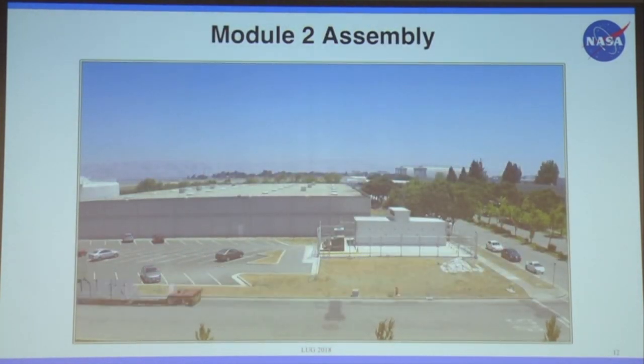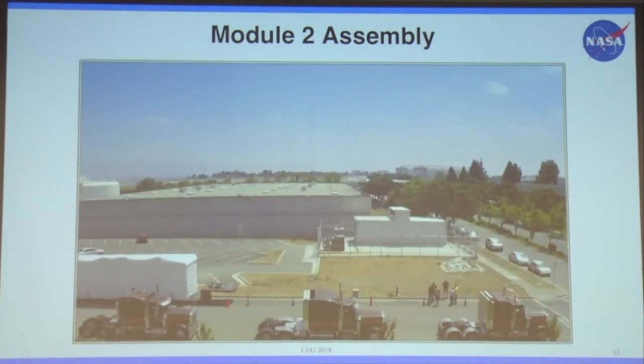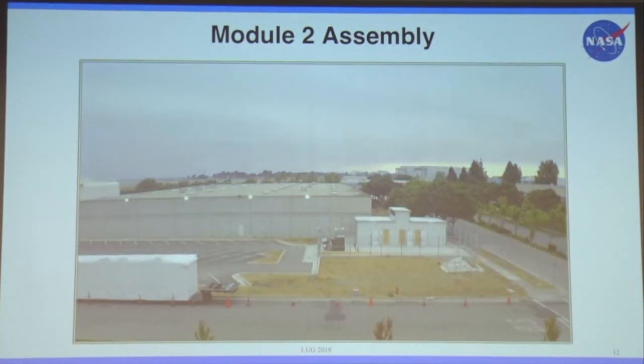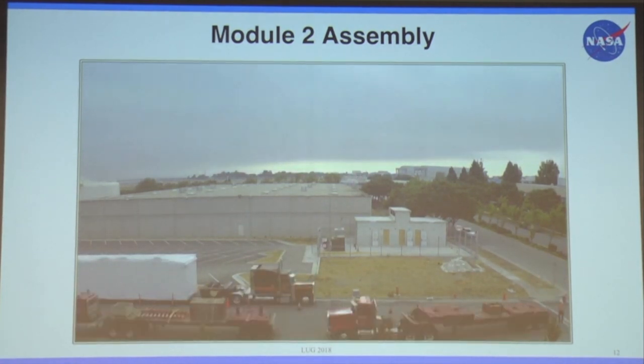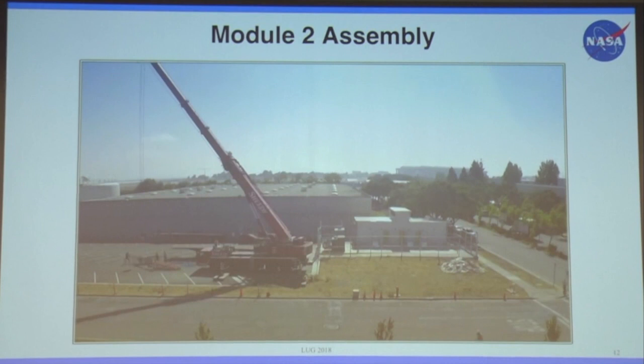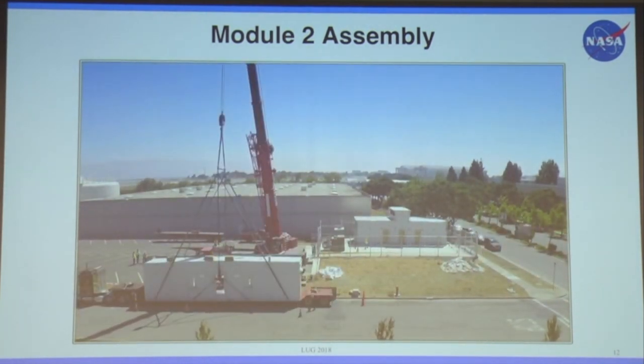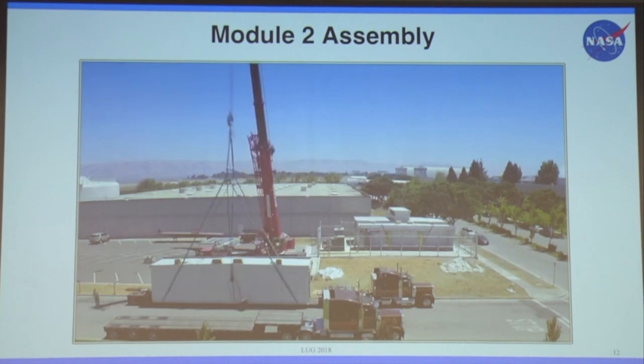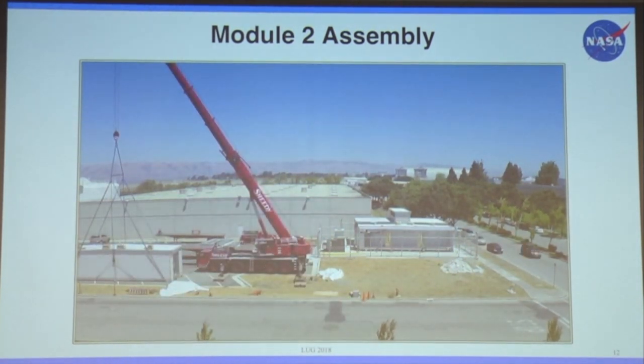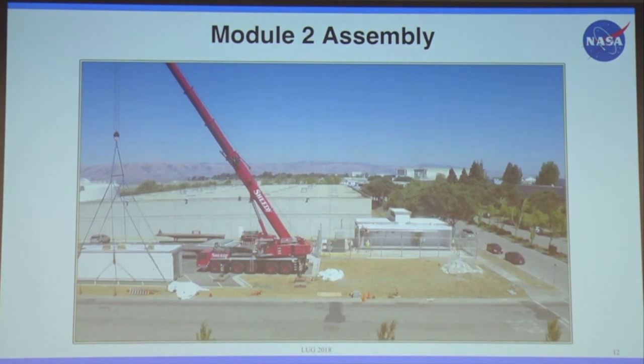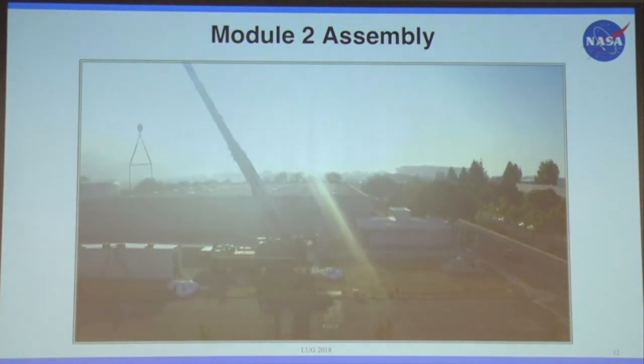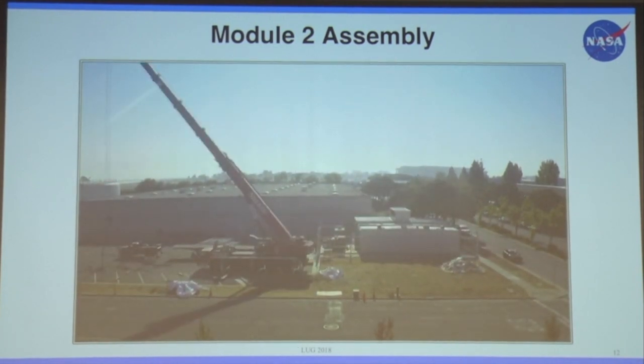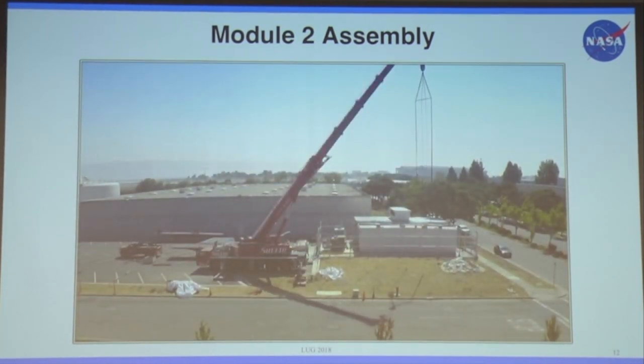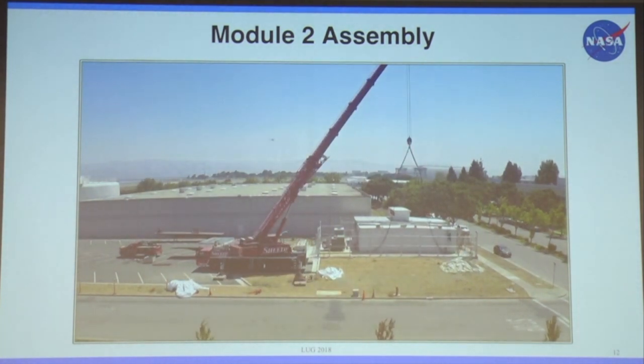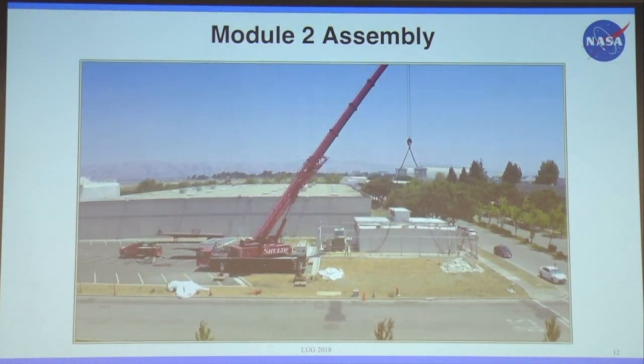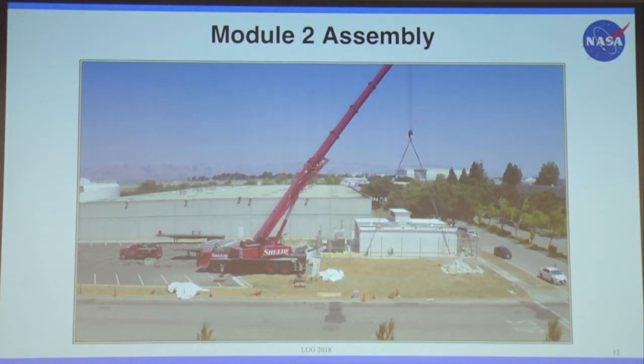This is actually the second module, and a little video time lapse of it coming in and being built. You can see the day to night transition over a period of about a week or so. You have this prefab facility that comes in, you assemble it, put chillers on top, which are dry air coolers, add about a megawatt of capacity, and that second module will hold on the order of 2,500 nodes. So this is the concept we're using to expand the facility beyond our current limits.